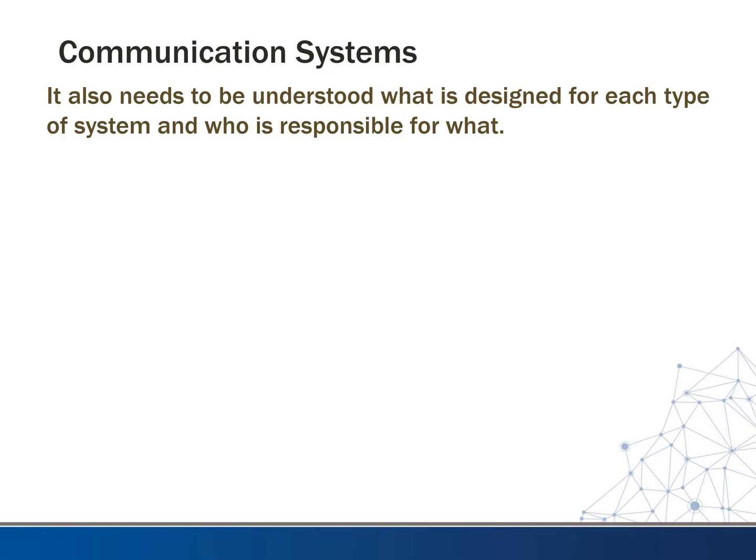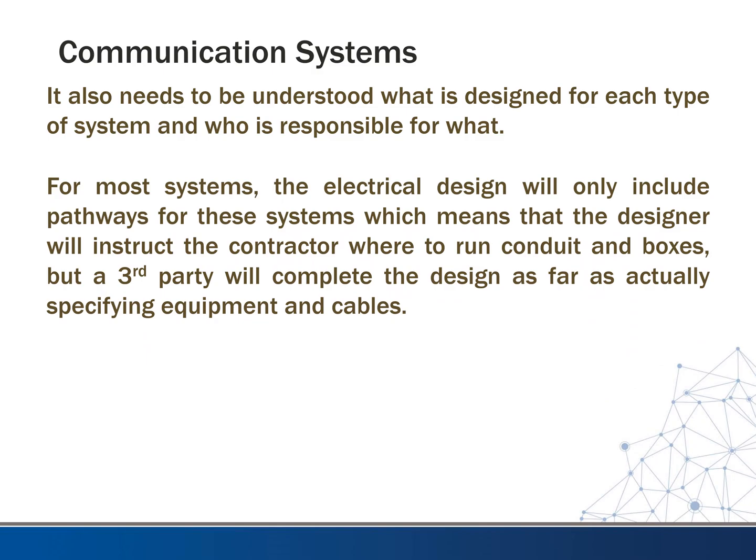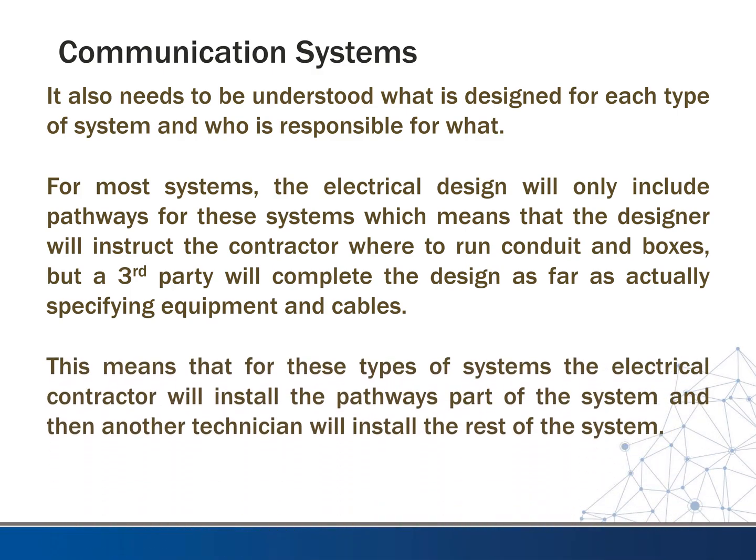It also needs to be understood what is designed for each system and who is responsible for what. For most of these systems, the electrical design will only include pathways — the designer will provide instructions in the design documents for the contractor on where to run conduit and set boxes. From there, a third-party entity will complete the design by specifying equipment and cables. The electrical contractor installs the pathways, then another technician installs the rest. Sometimes that technician works as a sub under the electrical contractor — usually the case with fire alarms — but for telecom, data, and security systems, that work is usually done after the electrical contractor is gone, hired directly by the owner.